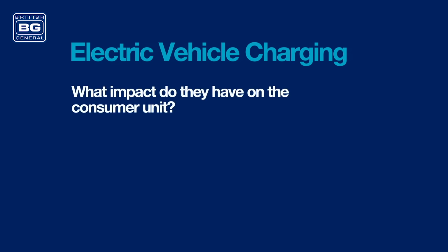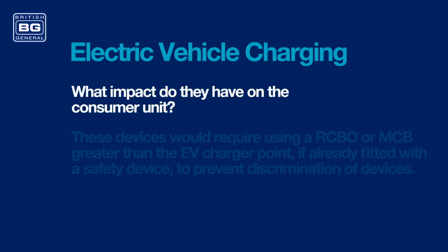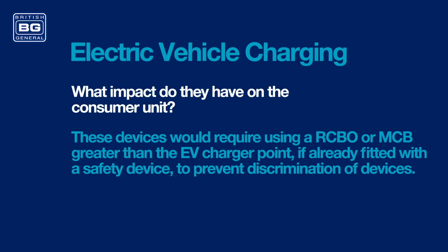What impact do they have on the consumer unit? These devices would require using an RCBO or MCB greater than the EV charger point, if already fitted with a safety device to prevent discrimination of devices.